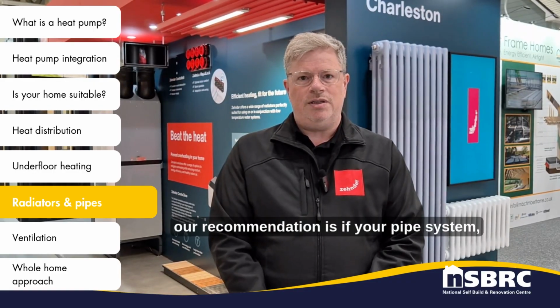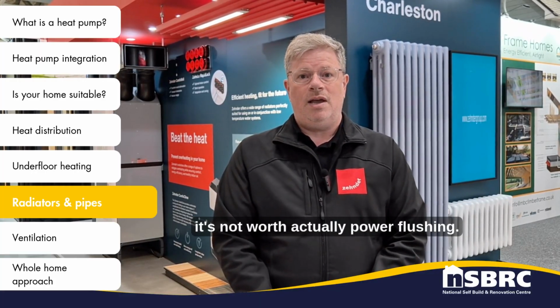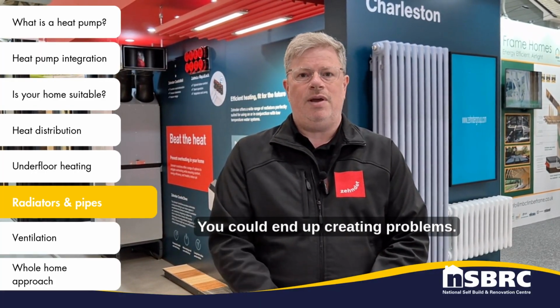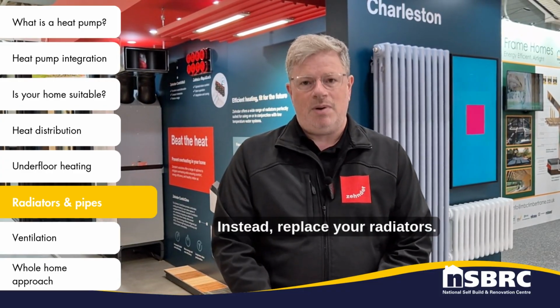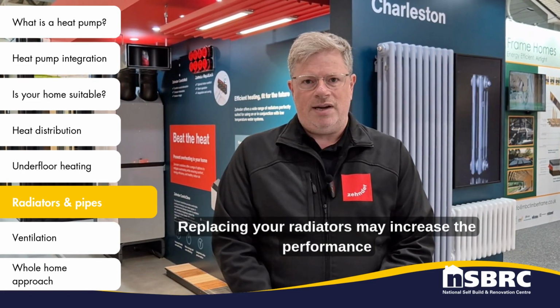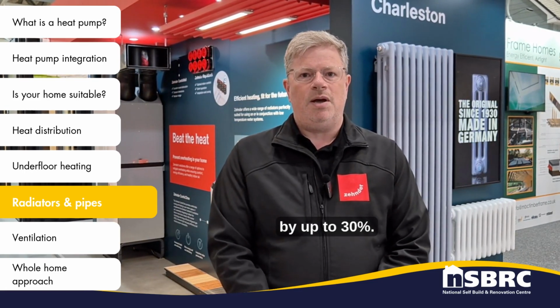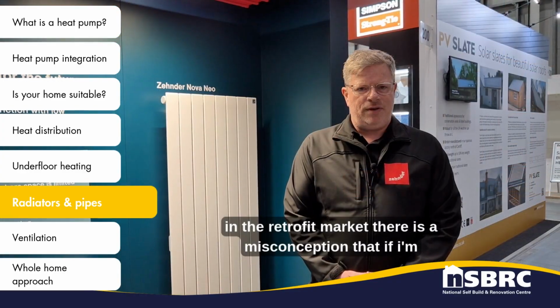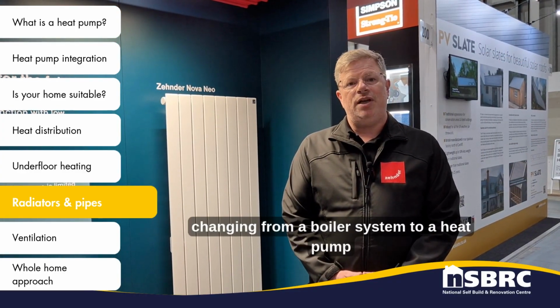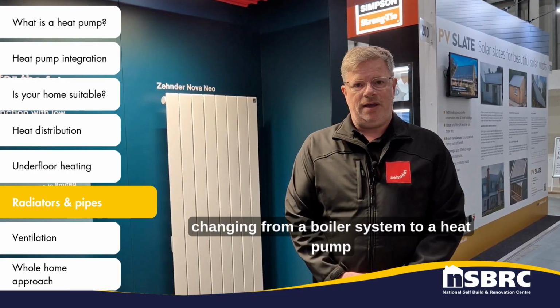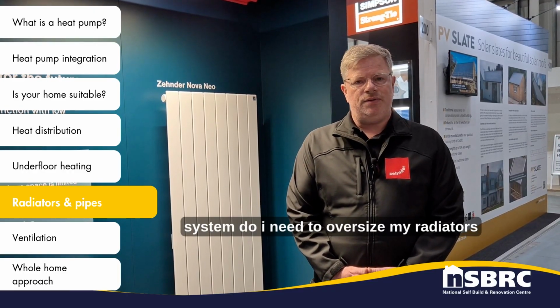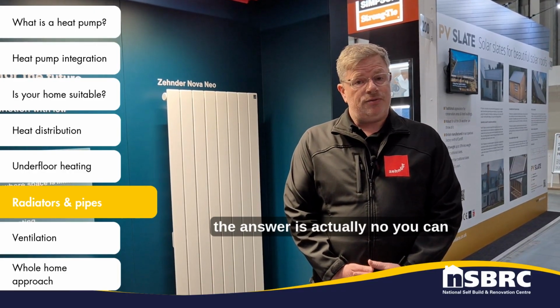Whilst using existing pipework, our recommendation is, if your pipe system hasn't been power flushed certainly for the last 8 years, it's not worth actually power flushing. You could end up creating problems. Instead, replace your radiators. That's the first challenge. Replacing your radiators may increase the performance by up to 30%. In the retrofit market, there is a misconception that if I'm changing from a boiler system to a heat pump system, do I need to oversize my radiators? The answer is actually no.